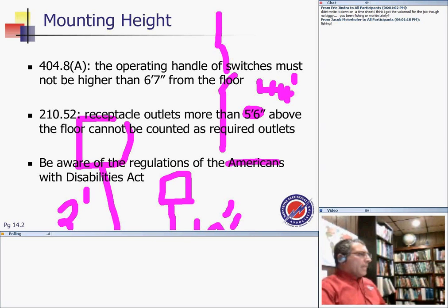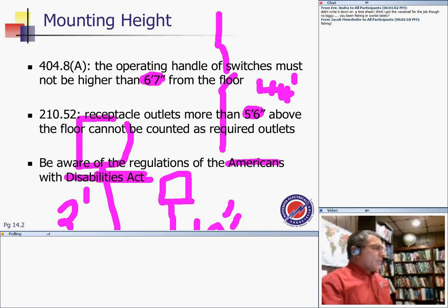How about the Americans with Disabilities Act? There's nothing in the code that tells you how high you can put your receptacles. There are recommendations, and a lot of these recommendations came from the Americans with Disabilities Act. It's 42 to 44 inches and so forth. But the heights of devices are just what counts and what doesn't count. You can put it higher than that.